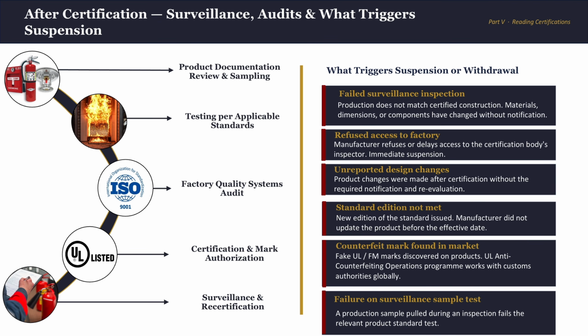And periodically, typically every 3 to 5 years, the products must be recertified against the current edition of the standard. And let's say a few years after my certification, everything worked perfectly fine. All my surveillance and audits are passing greatly. But let's say I'm out of a certain wood I'm using for my fire doors. If a manufacturer wants to change anything about the certified product, different raw material, different supplier, different dimensions, they must notify the certification body before making any single change, no matter how minor it is.